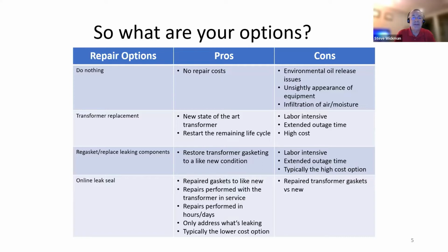Again, back to some of your options here. You can replace the entire transformer. Great, now you've got a new state-of-the-art unit and you can restart your remaining life cycle, but it's a pretty labor-intensive exercise. The outage can be measured in months, and it's pretty costly. And I think Drew alluded to this too: lead time on getting large power transformers these days is apparently an excessive number of months, probably even longer than a year. So replacements have got to be planned quite a bit in advance.